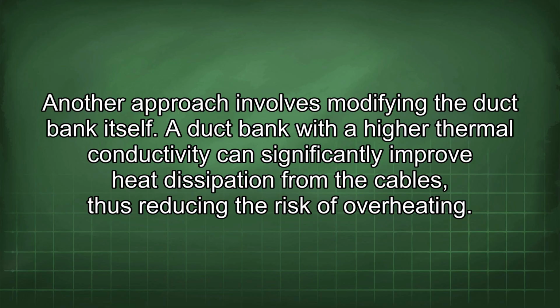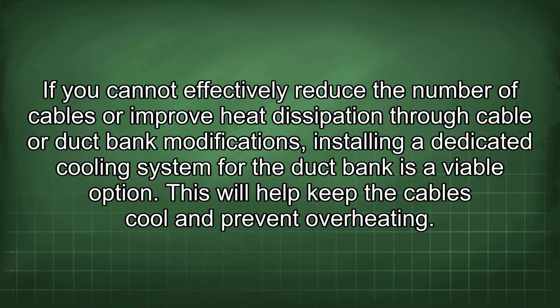Another approach involves modifying the duct bank itself. A duct bank with a higher thermal conductivity can significantly improve heat dissipation from the cables, thus reducing the risk of overheating. If you cannot effectively reduce the number of cables or improve heat dissipation through cable or duct bank modifications, installing a dedicated cooling system for the duct bank is a viable option. This will help keep the cables cool and prevent overheating.